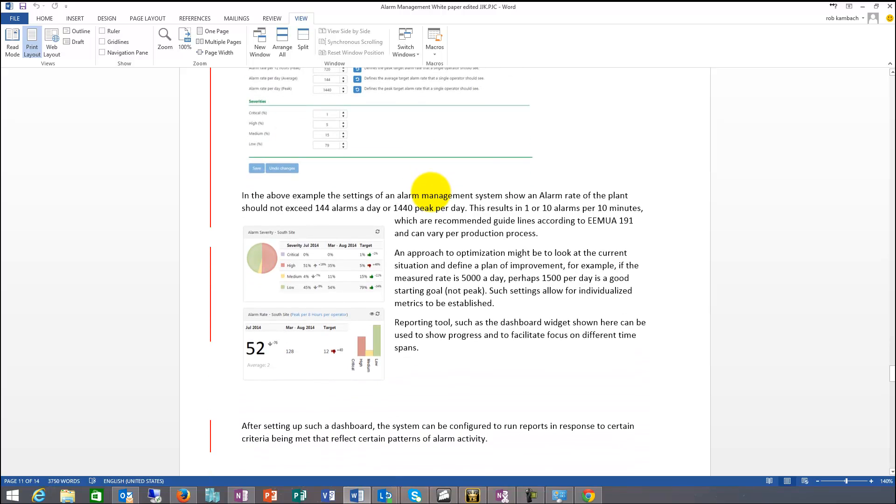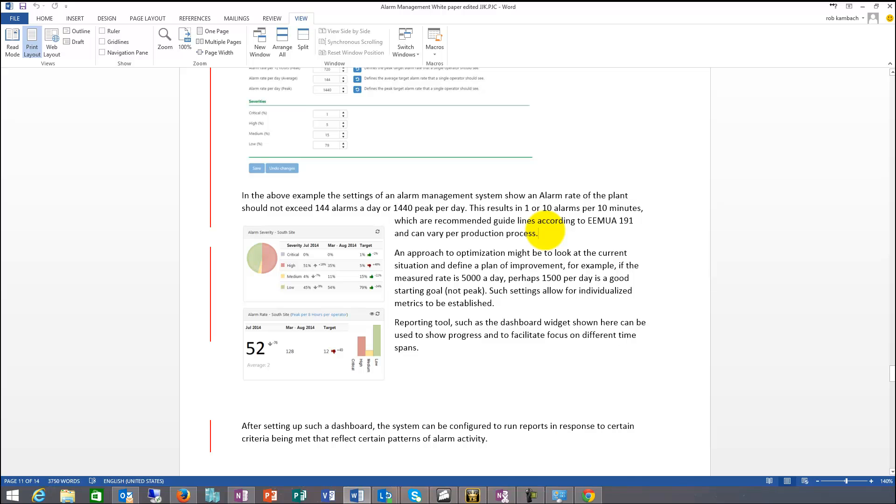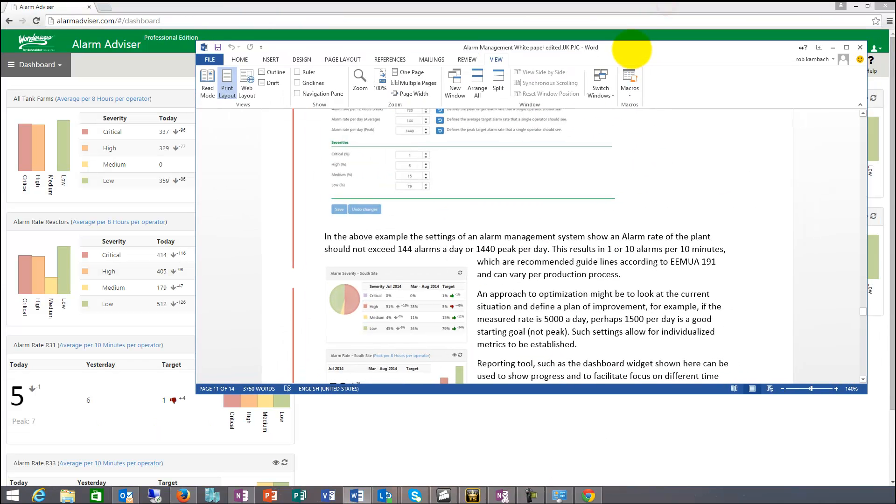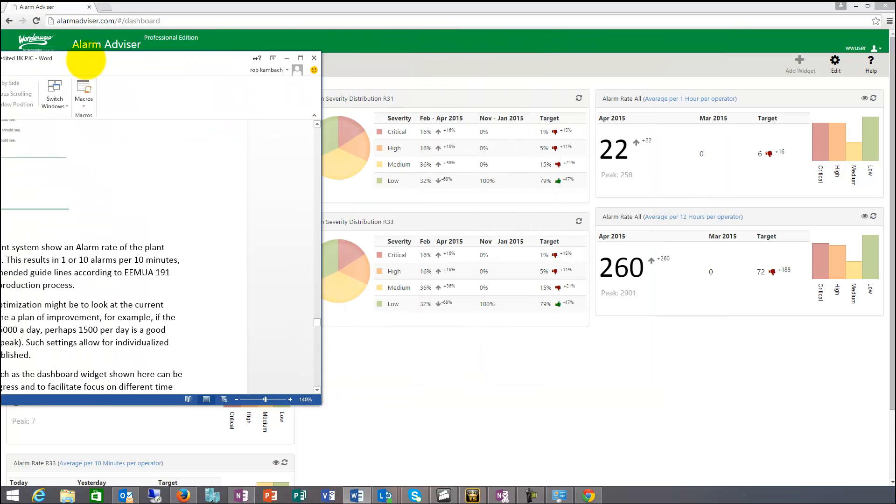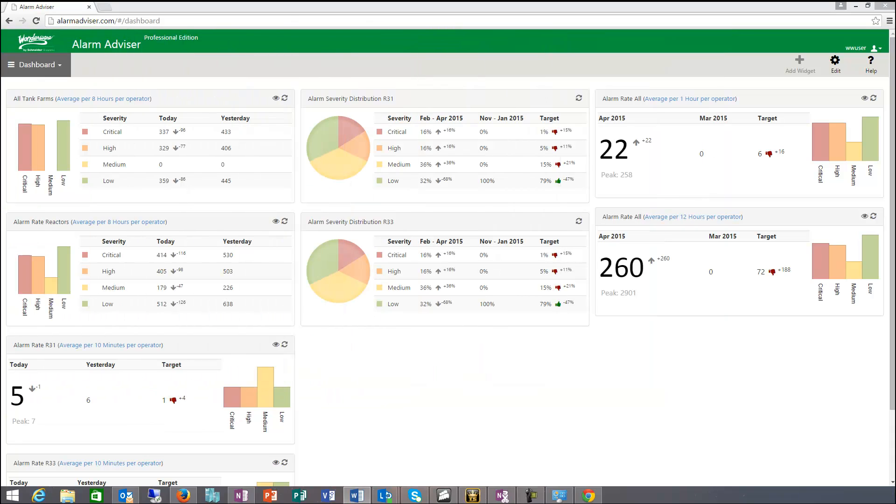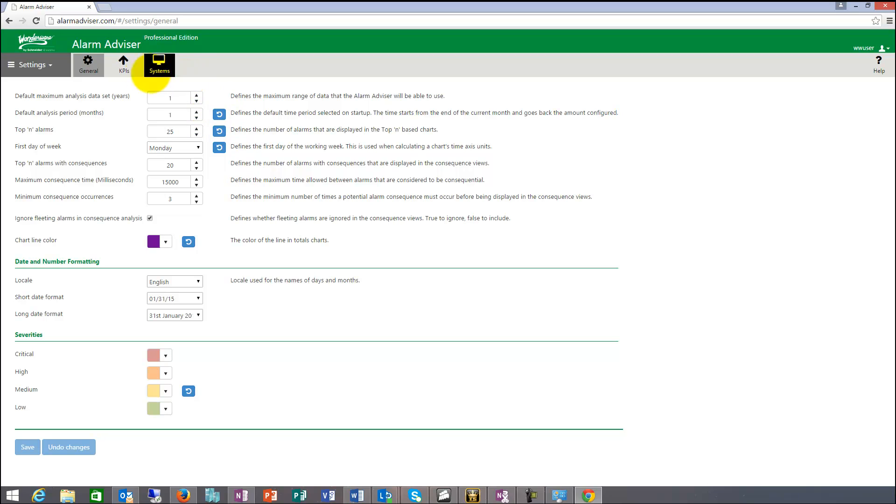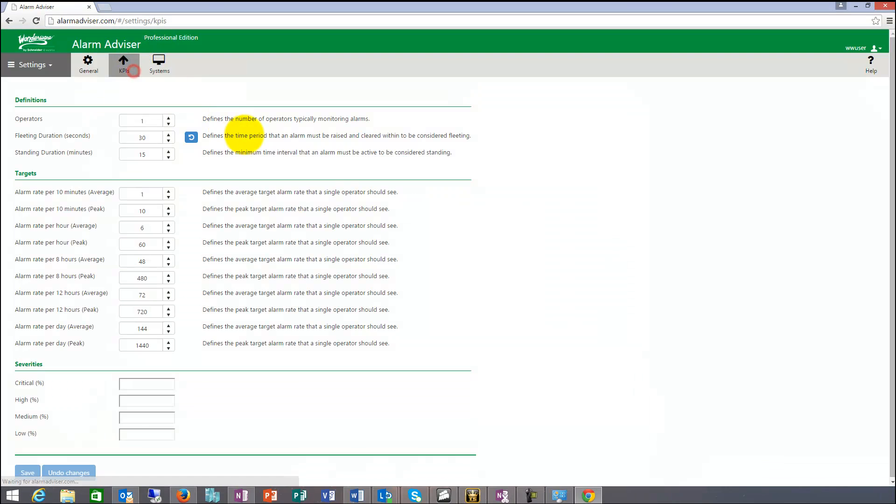If you look at the EEMUA there are 1440 alarms peak per day, 144 alarms a day in regular mode. One to ten, one or ten alarms per ten minutes. One alarm is average, ten alarms is peak. Which are recommended guidelines according to the EEMUA and but they can vary by process and by location. So the first thing in alarm advisor would probably be to set up these settings towards your facility.